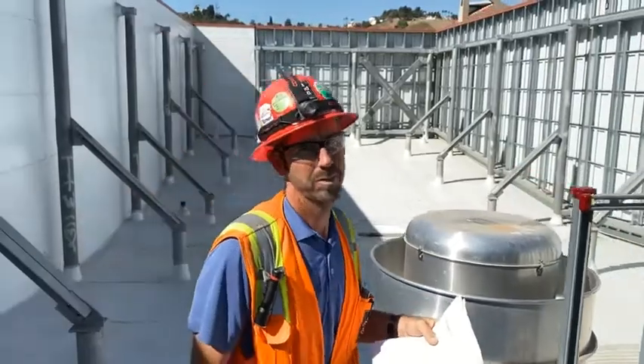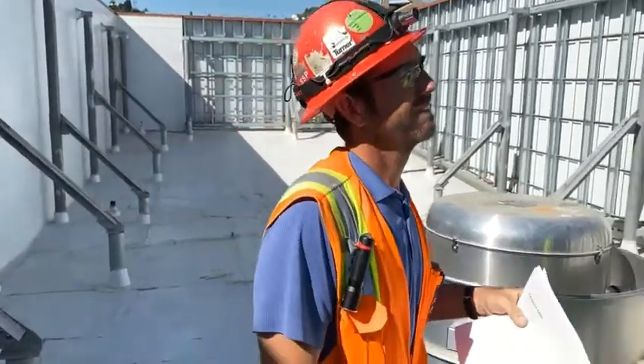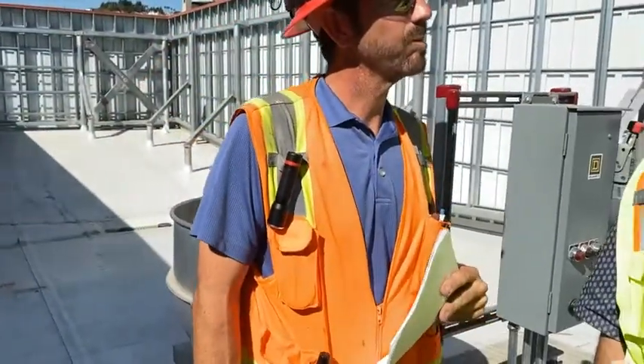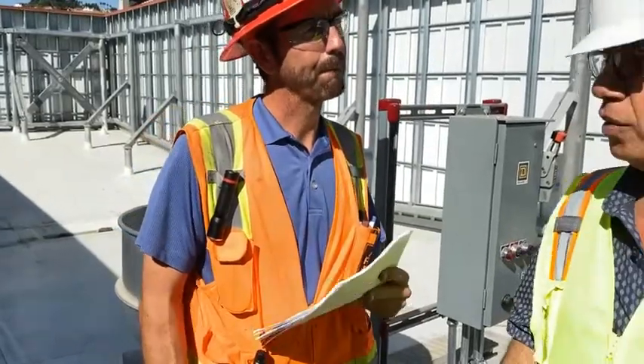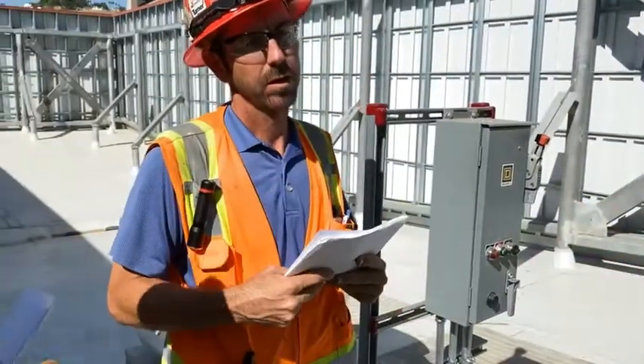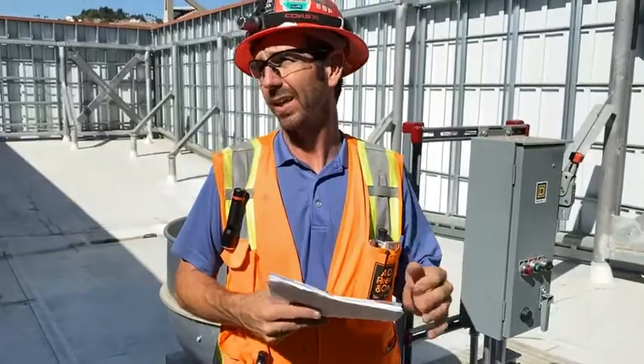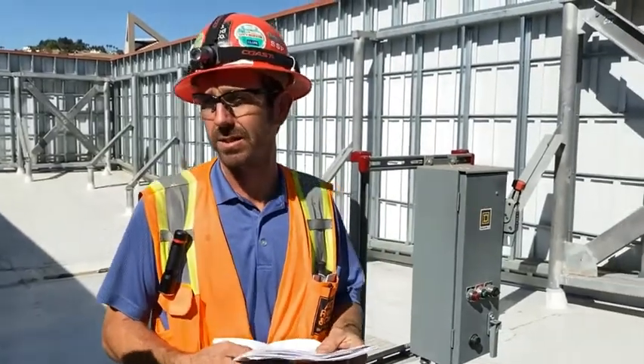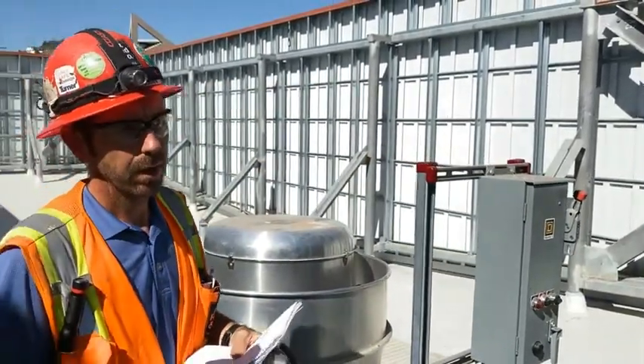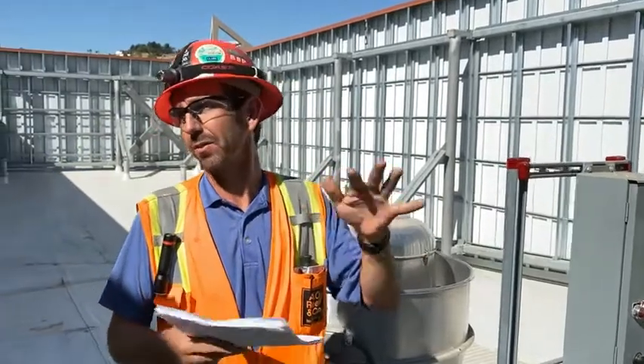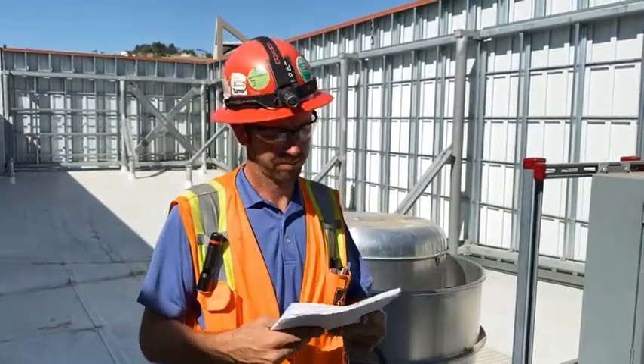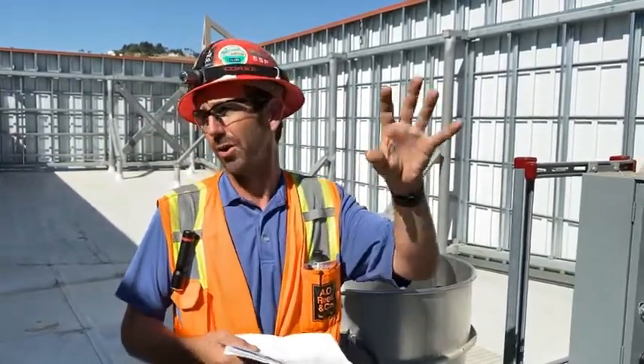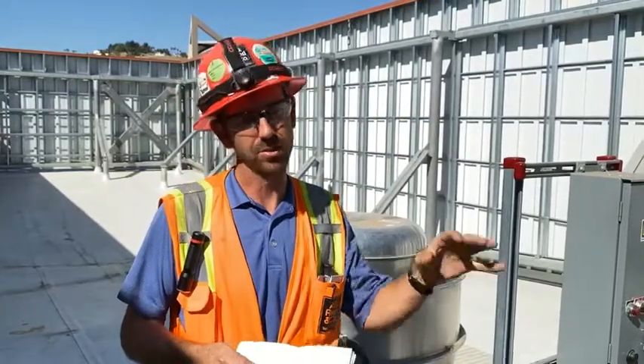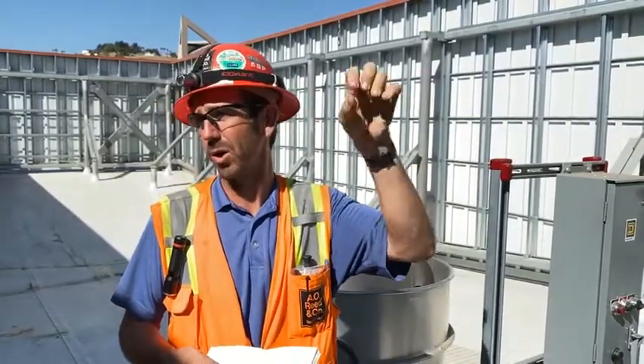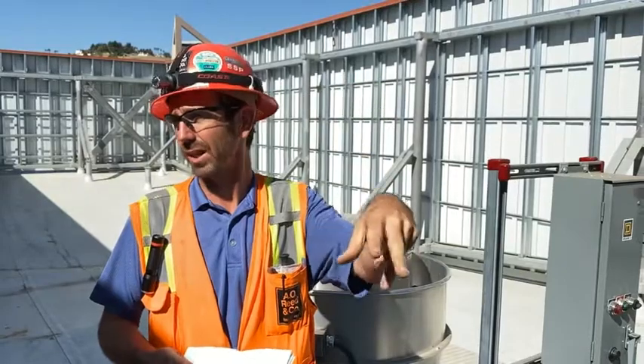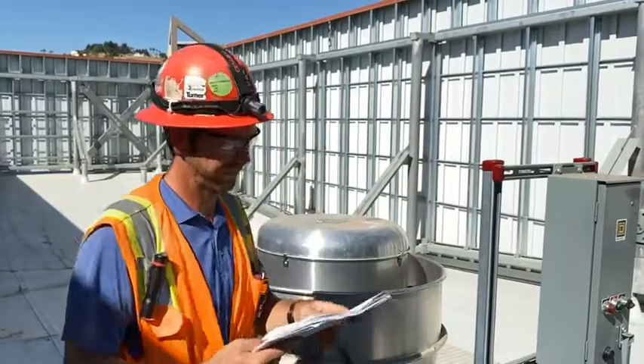Still going? Okay. What was the word for this, for the evaporator? I'm sorry? The whole name for that unit. The name of that unit is an air handling unit. It's not the evaporator. No, there's no evaporator. That's like for a refrigeration circuit. That just has a chilled water coil in it. Okay, we're just using cold water, passing it through the coil, blowing air across that, creating the cold air for the space.